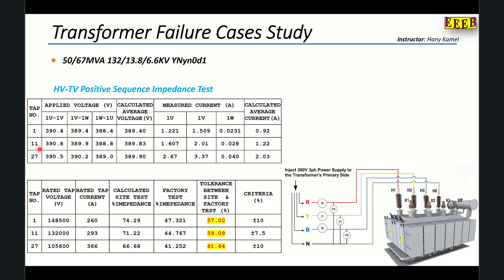When we perform it at the electrical center tap — tap 11 — we notice the same pattern: current in H1 and H2, but no current in H3. Then at tap 27, the same result with very low or no current in H3. We then calculate the impedance percentage, compare it to the factory value, and find the error between site and factory. As per IEC standard, the error exceeds the acceptable limit for short circuit impedance.